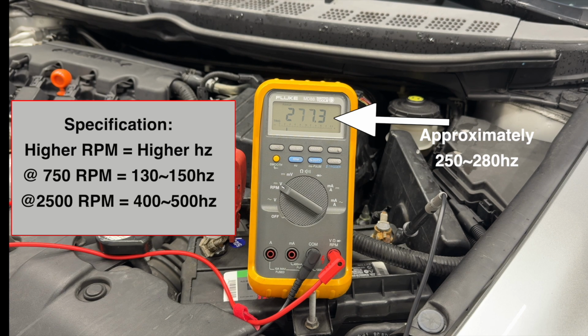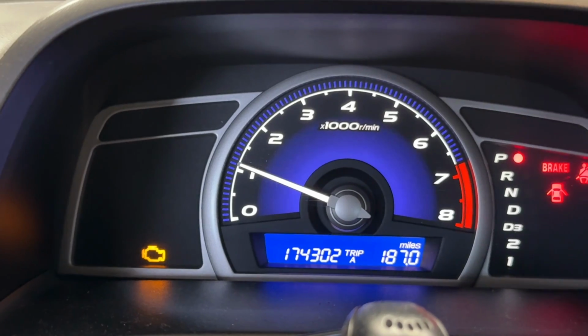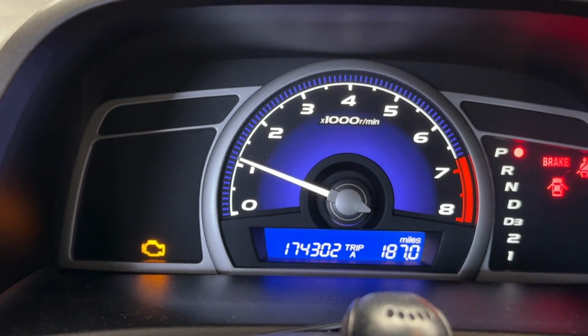So I've got 275, and the spec is 130 to 150 Hertz. My idle's quite a bit higher, it's at 1300 RPMs, and it says 750 RPMs should be 130. As RPM increases, frequency also increases.